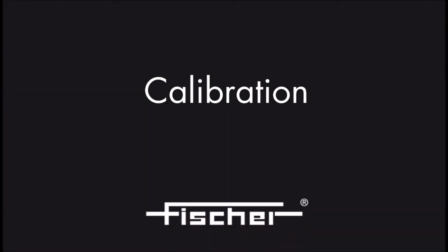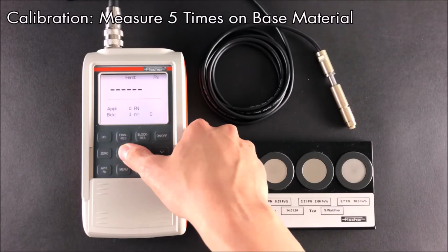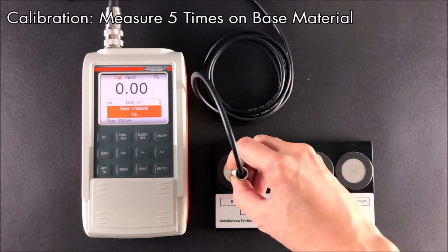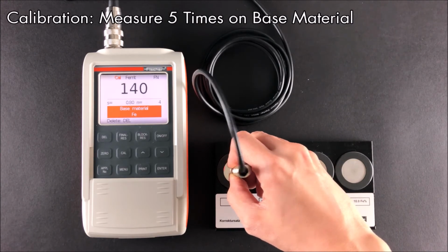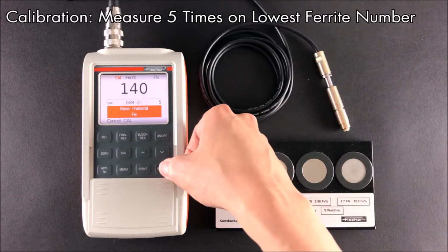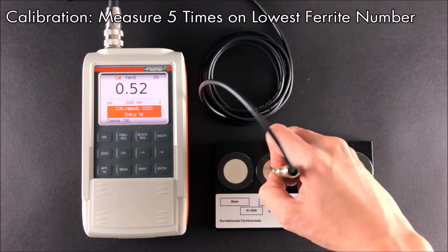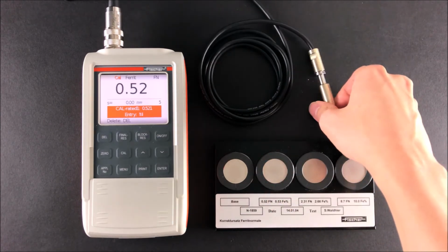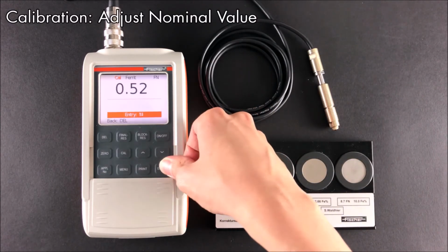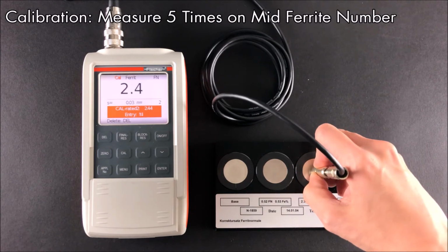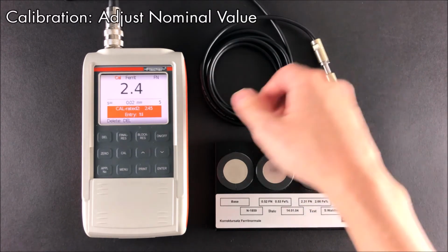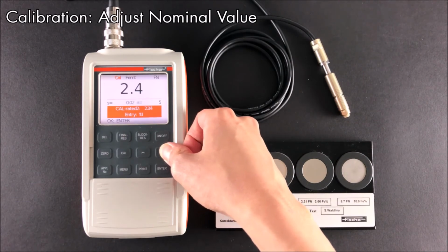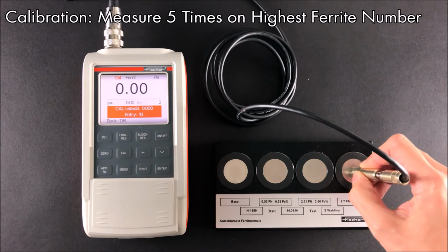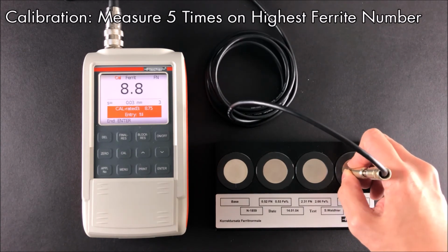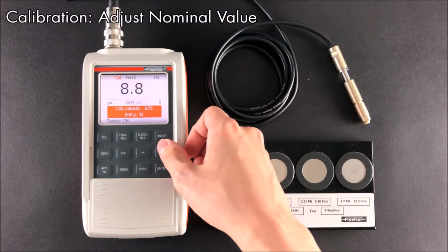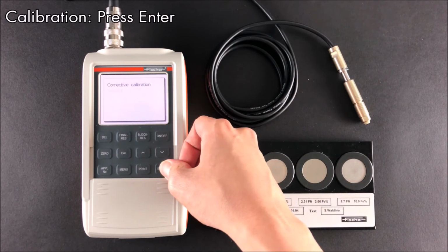Next, I will perform a calibration. Measure the base 5 times. Next, measure the calibration standard with the lowest ferrite number 5 times. Adjust the nominal value of the calibration standard. Next, repeat the same steps for the remaining calibration standards with increasing ferrite concentration. The calibration is complete.